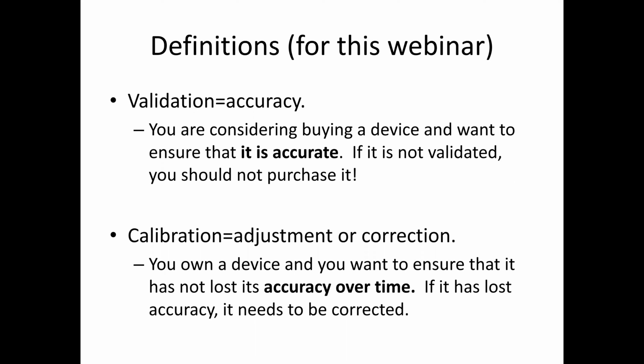The second is calibration, which is, I guess, equally important. Now, calibration, you'll run into that when you have purchased the device. So you own a bunch of devices, and when I say device, it could be an aneroid sphygmomanometer as well. And you want to make sure that over time, that device is not losing its accuracy. And that is what we refer to by the word calibration and the process of calibration. And I'm going to be going over that in a few slides as well. So next slide then, Lindsay.